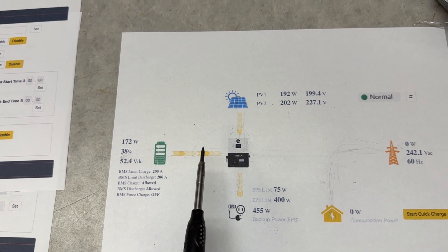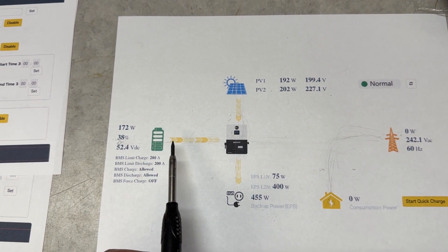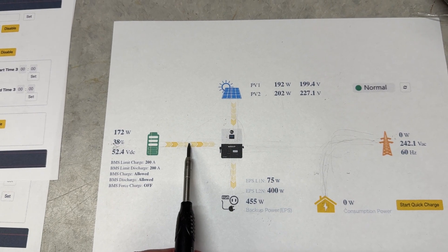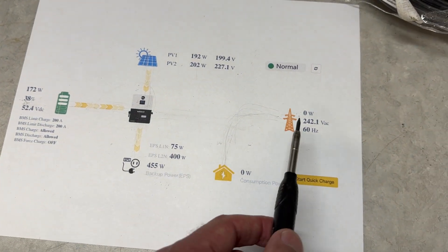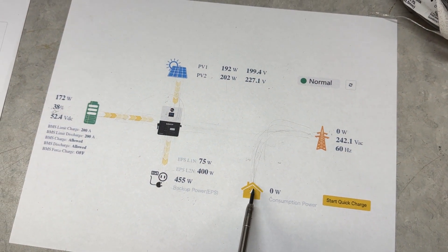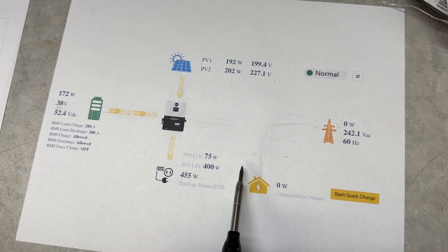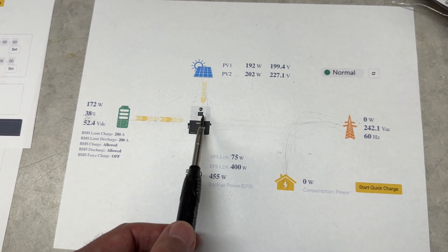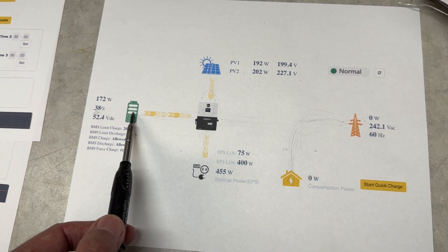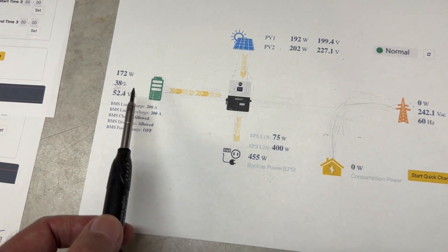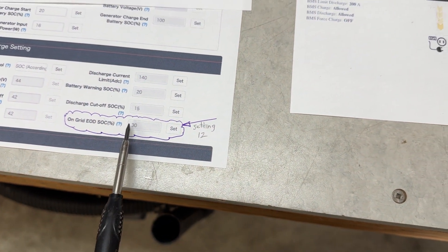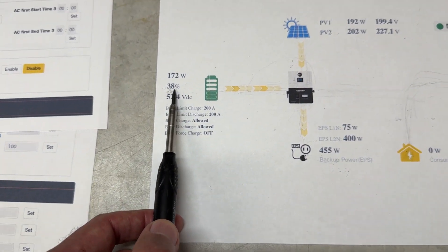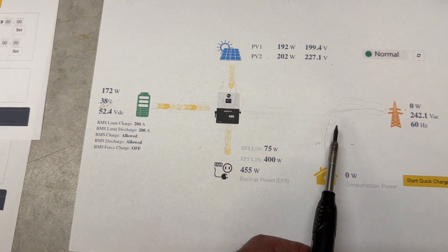When it gets down to the 29 percent, this will turn off—again assuming there's no power generated here—it'll go into bypass mode. Then when the sun comes back up and there's power being generated here, it will start charging the battery. When the battery gets to 10 percent above your power setting here, so in this case when it gets to 40 percent, then it will remove the bypass.